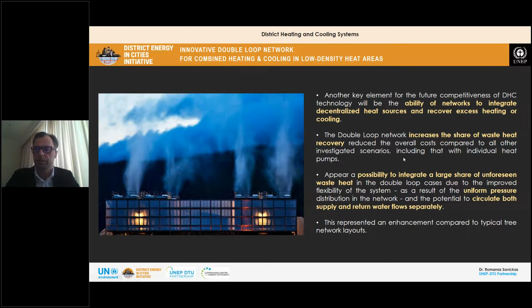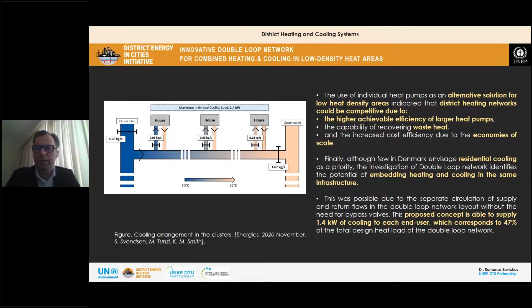When comparing individual heat pumps and district heating networks, the use of individual heat pumps as an alternative solution for low heat density areas indicated that district heating networks could be competitive, because of the higher achieved efficiency of larger heat pumps and the capability of recovering waste heat, which increases cost efficiency due to economies of scale. It's also possible to separate circulation of supply and return flows in the double loop network. The proposed concept is able to supply 1.4 kilowatts of cooling to each end user, corresponding to about 50% of the total designed heat load of a double loop network.